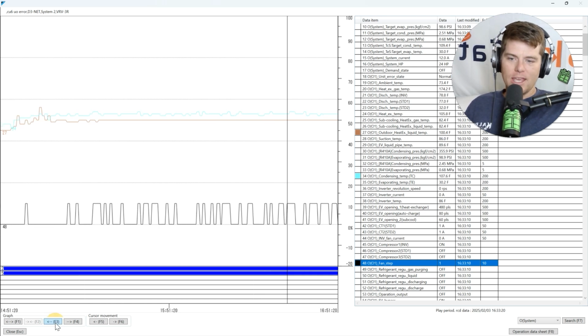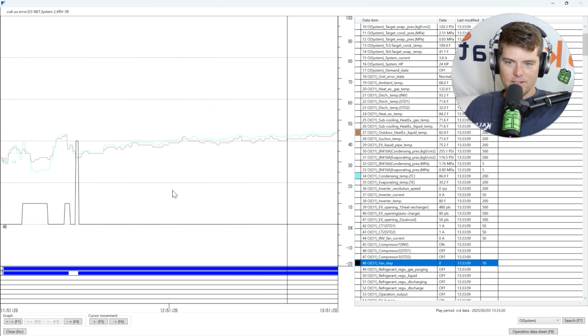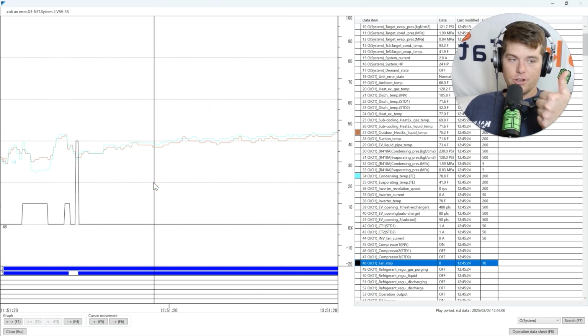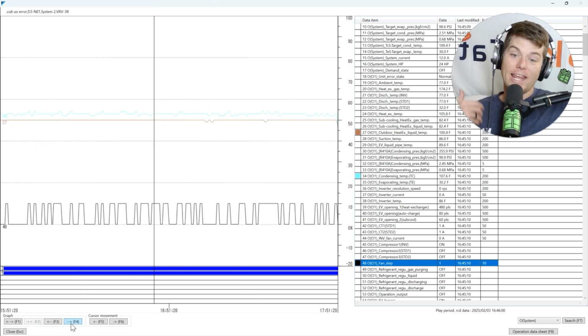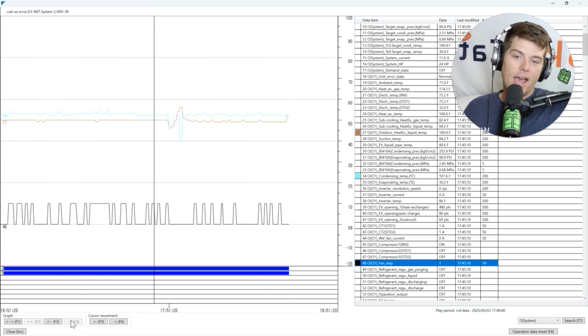If I go back to the beginning, remember, in the 26 minutes that I looked at, it was good discharge superheat within range, good suction superheat within range, subcooling within range, and guess what? The fan wasn't running, which is kind of a red flag, but again, you can't troubleshoot in the first 26 minutes. This is an overtime, how does it progress? And it gets worse, and it gets worse, and it maintains with no fan speeds running. This system, again, undoubtedly undercharged.